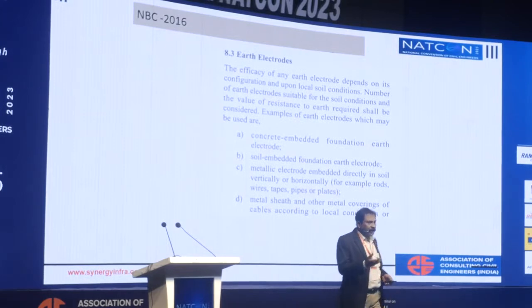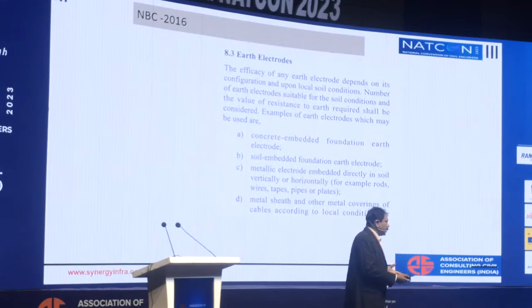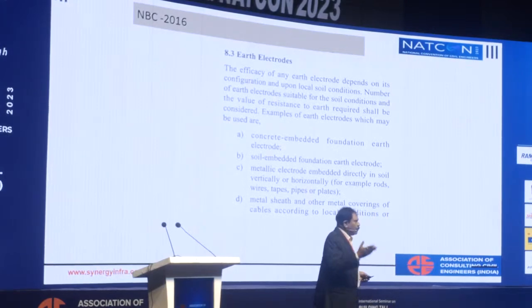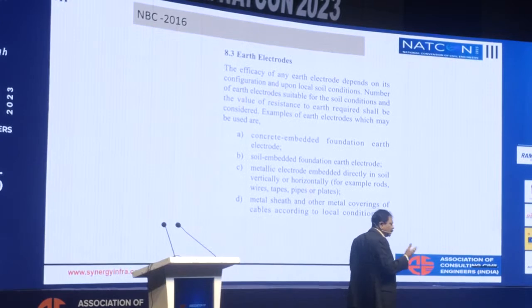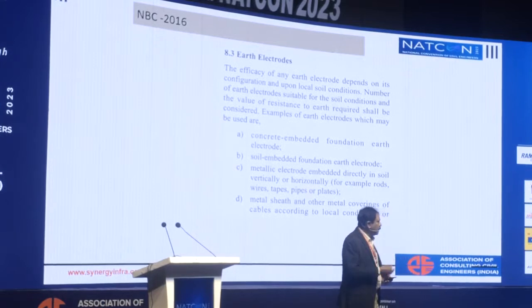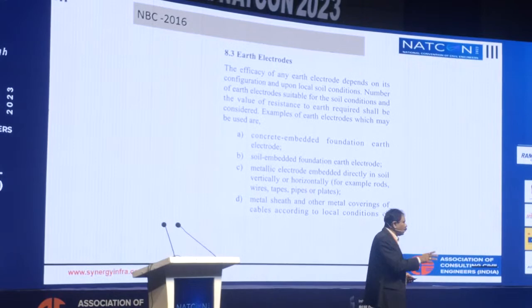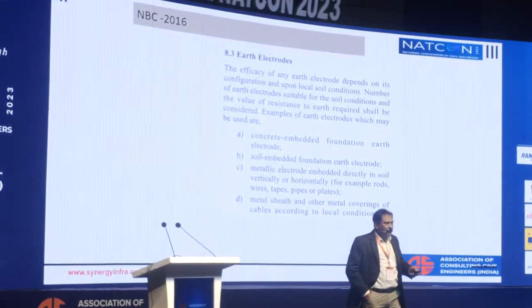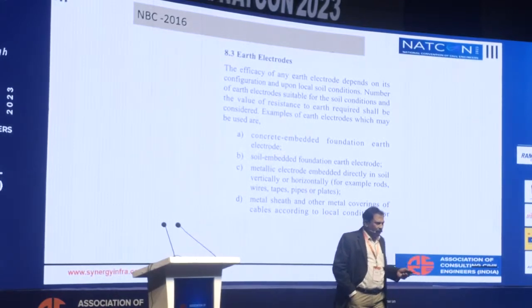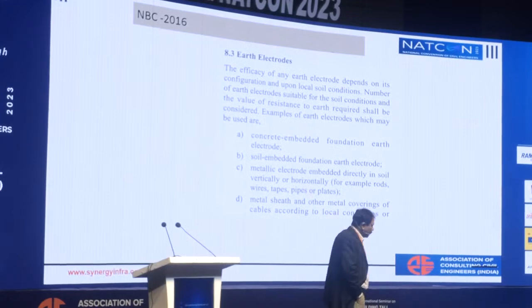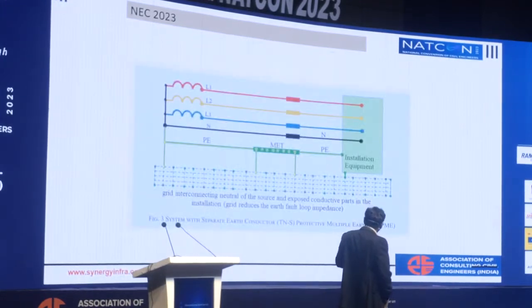In fact, concrete works as a very good conductor. We look at the soil resistivity. It may vary from 10 ohm meters to around 1000 or 2000, depending on the type of soil. In some sandy soils it may go up to 4000 ohm meters, and rocky soils up to 10,000 ohm meters. But concrete is generally around 100 ohm meters, and we can also get very good resistance using the concrete. So the concrete encased electrode is one of the methods preferred by the codes.